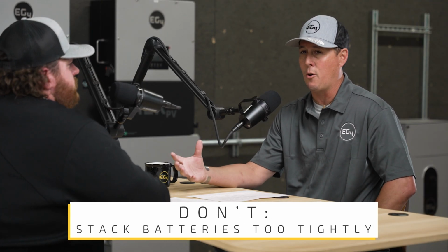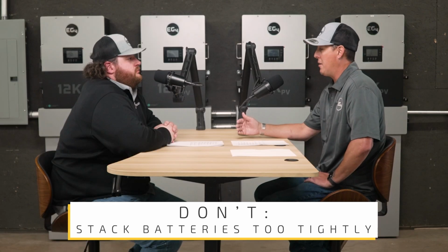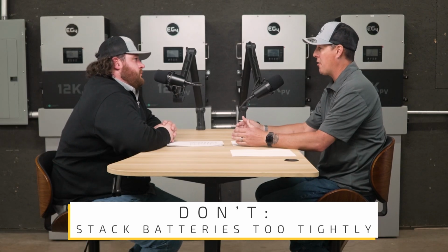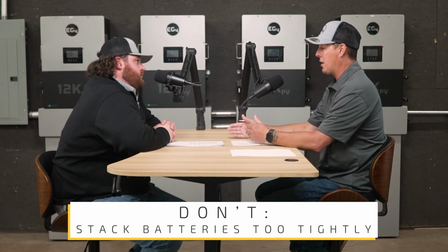Don't stack your batteries too tightly. This kind of goes into your heat dissipation. You don't want to put your equipment so close together that if one inverter is blowing out hot air, you don't want the other inverter pulling in that hot air. You want to have some separation to make sure we're allowing proper ventilation for those systems so as not to overheat them. Again, that kind of goes back into that south-facing wall.